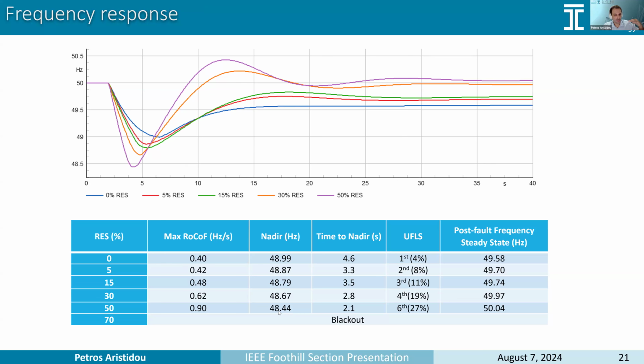And then every 0.1 hertz, it moves to the next stage. So cumulatively, it goes to 27%, and that's a very big reduction in the load that covers, let's say, the lost generator. And we actually stabilize, and the post-fault frequency is higher than 50 hertz. That is the reason. But that's the reality. That's something that we have seen in recordings of events in the system.